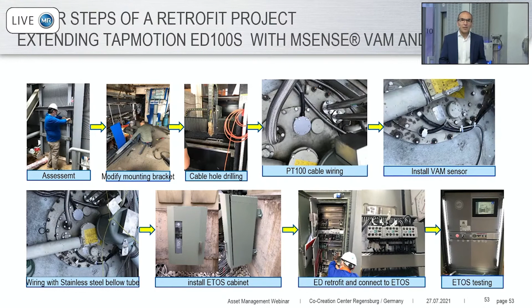For the OLTC monitoring, a few steps were done in advance. The site assessment to inspect every single transformer and substation. Once that site assessment was conducted, within a few days, this entire process took about 3 days, the brackets for the mounting of the cabinet were executed. The routing of the communication and data cables, signal cables, was executed. The mounting, as I indicated, on the OLTC for the temperature.